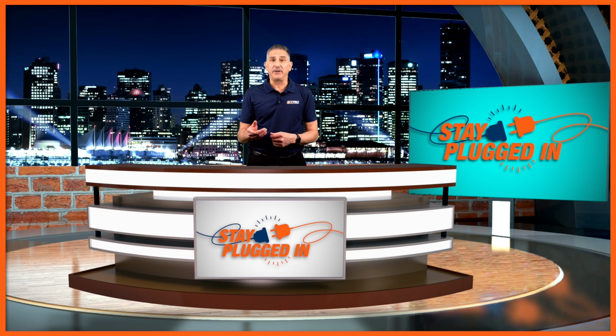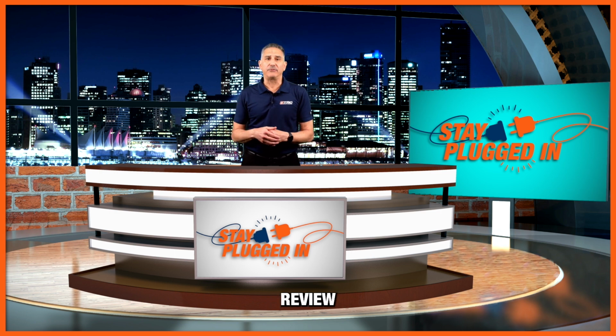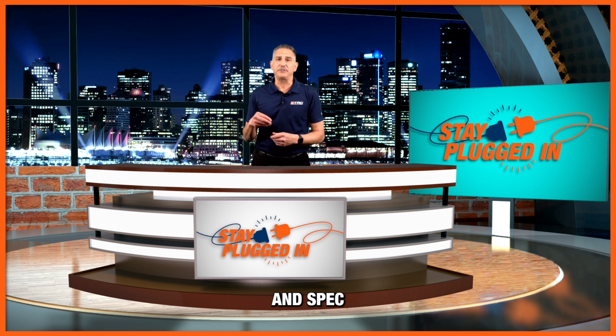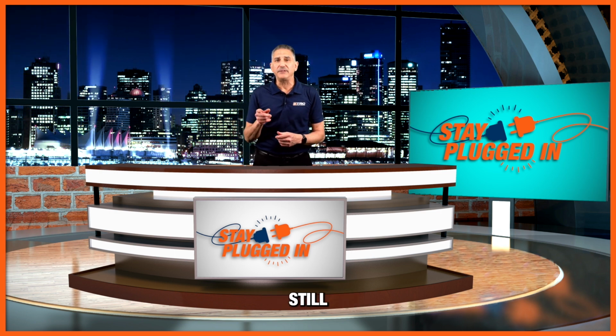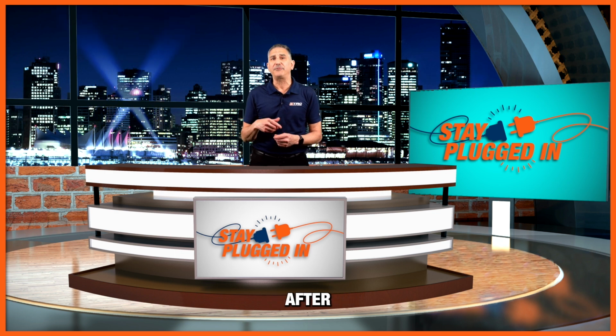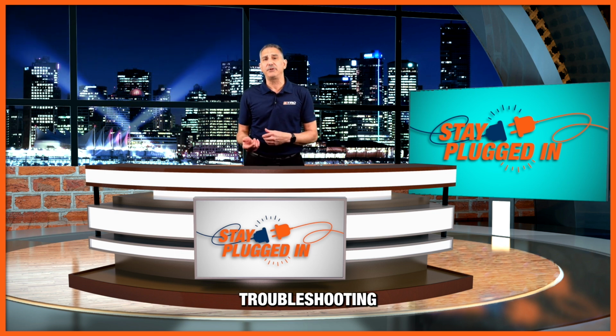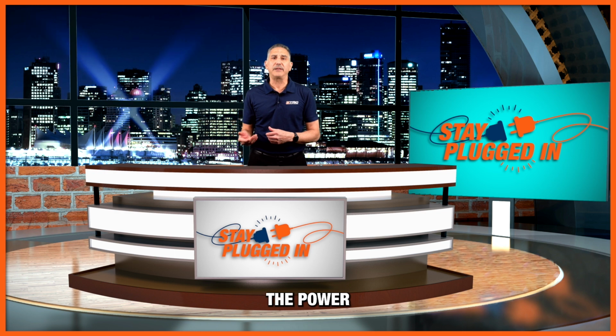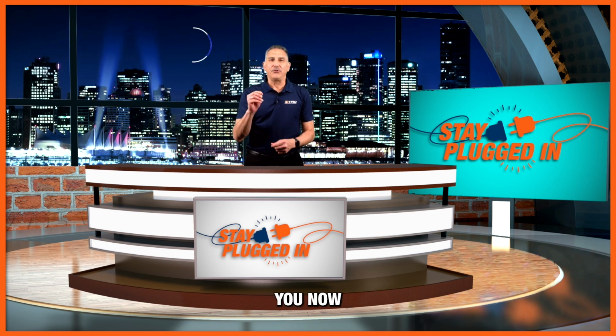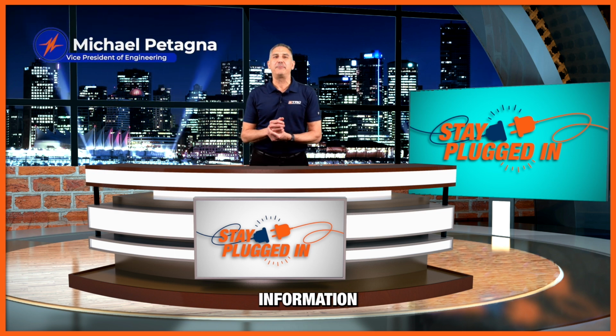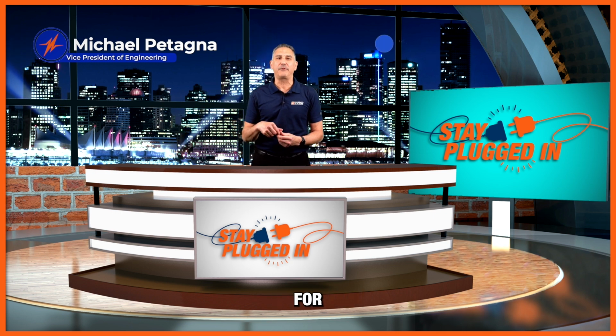If all of these items check out, review the power supply documentation and spec sheets. If your supply still fails to respond after running through these quick troubleshooting procedures, we can be certain that the power supply is dead on arrival. You now have all the necessary information to communicate with the supplier for a return.